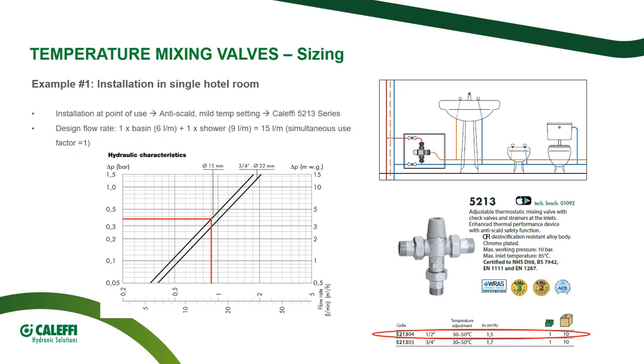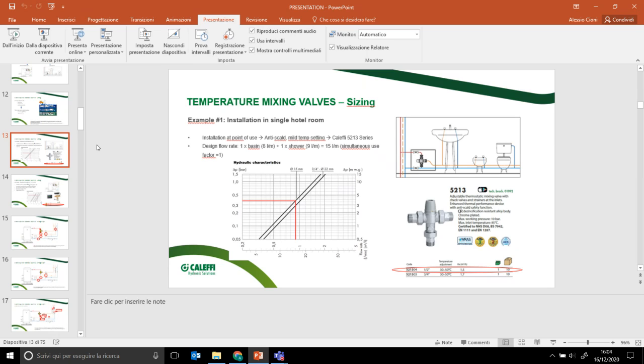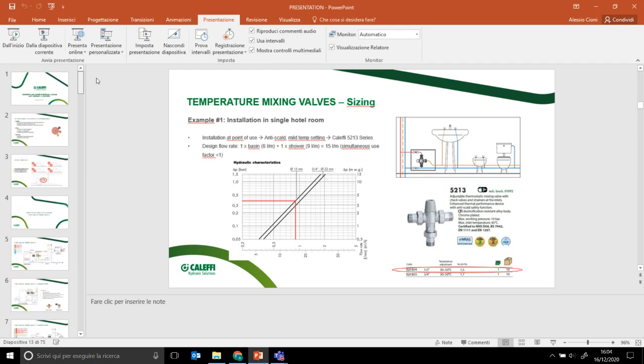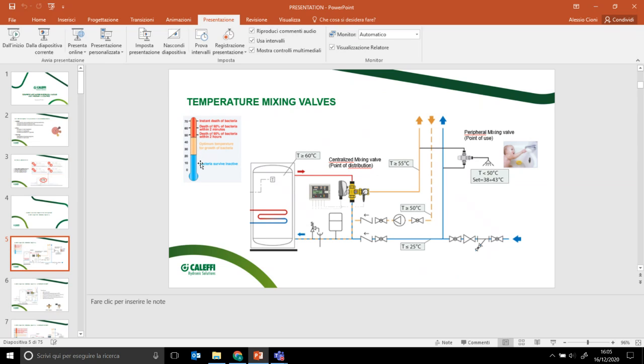Okay. Next one. In hot countries, would the emphasis be reducing the heat gain in the cold water supply in the domestic water system? I don't really understand this question actually. Me neither, but probably they want to mention that you might have Legionella problems even in the cold water line. It might happen in your country where cold water in summer is not cold, so it is warm. So reaching values of more than 25 can be easy. So our suggestion is to forecast a system to cool also the cold water in summer season. Maybe a heat exchanger or some very prestigious installation.